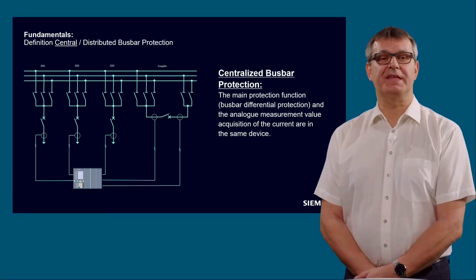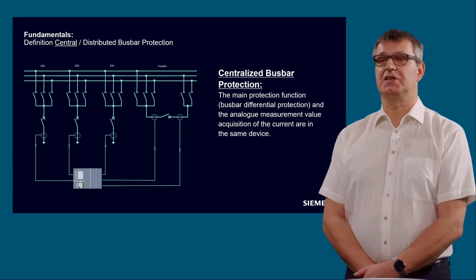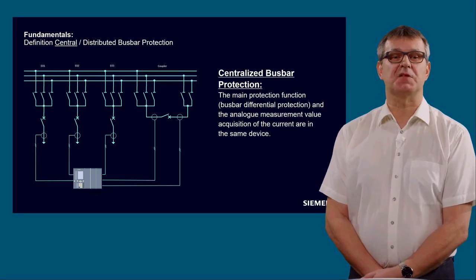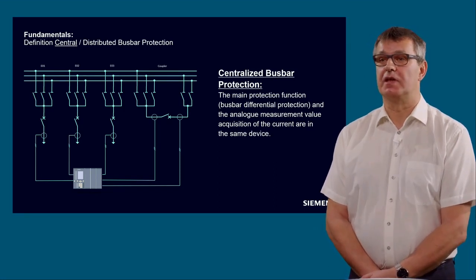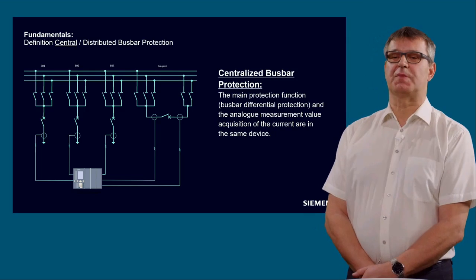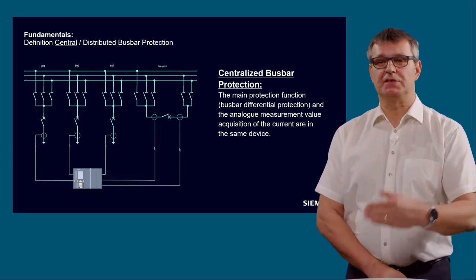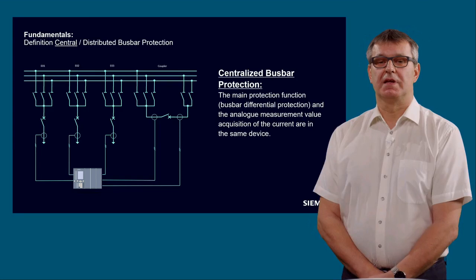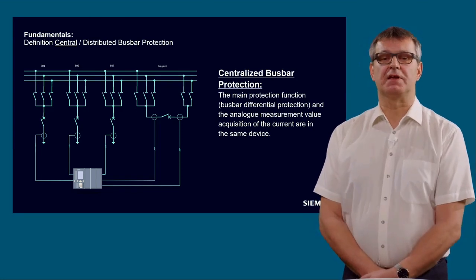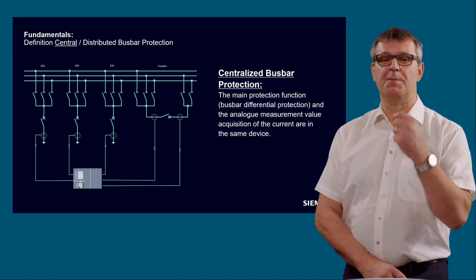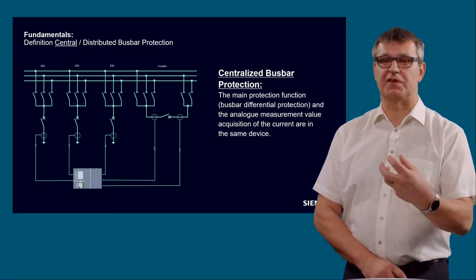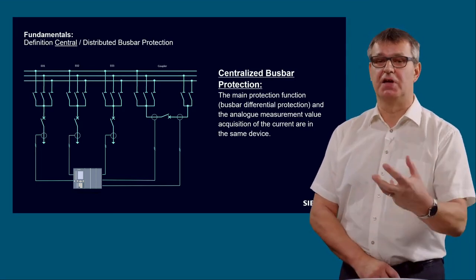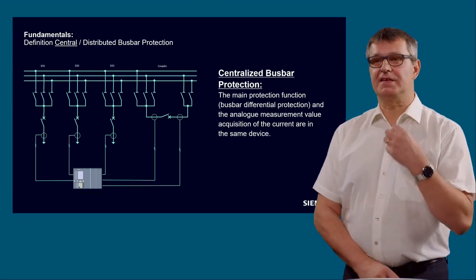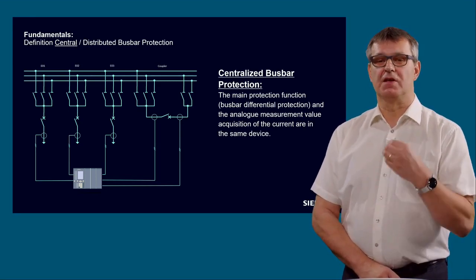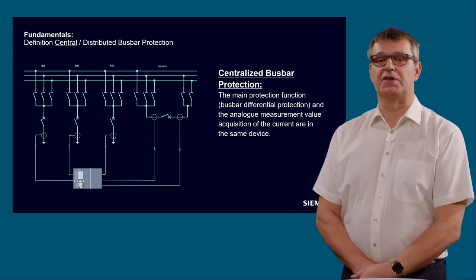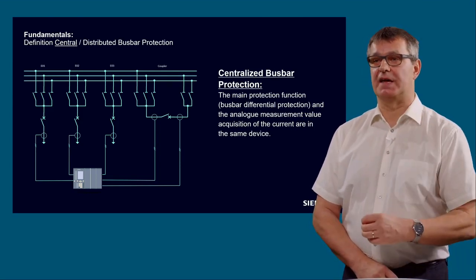Some further basic definitions. What exactly is a centralized busbar protection, and in contrast, what is a distributed busbar protection system? Let me first read the definition. A centralized busbar protection is one where the main protection function, the busbar differential protection, and the analog measurement current value acquisition are in the same device.